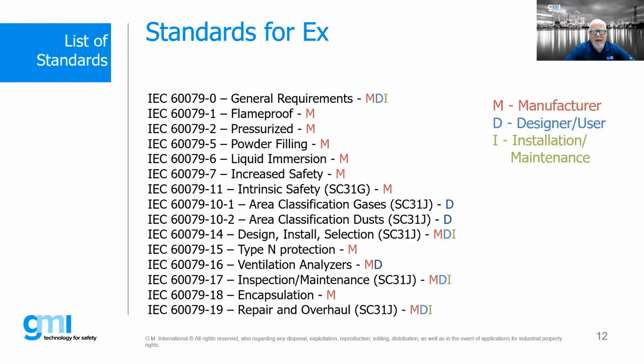The one standard that I think is really important, that a lot of people have questions about, is the dash 14 standard. This covers the design, installation, and selection of EX equipment. Competency programs like IEC EX, COPC, or COMPEX are very much based upon the dash 14 standard. Here in the United States, a lot of designers, installers, and contractors use the National Electric Code, and we follow articles 505 or 500 through 516 for designing systems for hazardous locations. The dash 14 is really a very similar type of document.